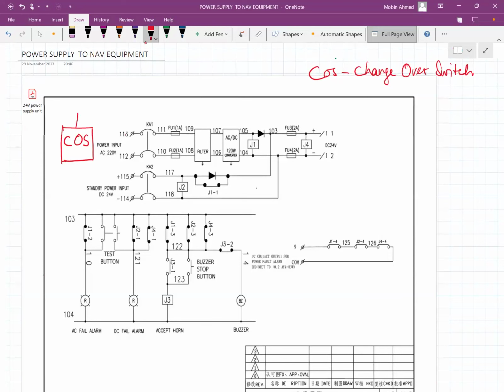Now the changeover switch gets the mains supply, that is the 220 volt from the MSB, and the emergency 220 volt from the emergency switchboard, ESB. Always the mains will be connected, but if the mains is interrupted or disconnected, then the emergency source of supply will be connected. So this is the changeover switch.